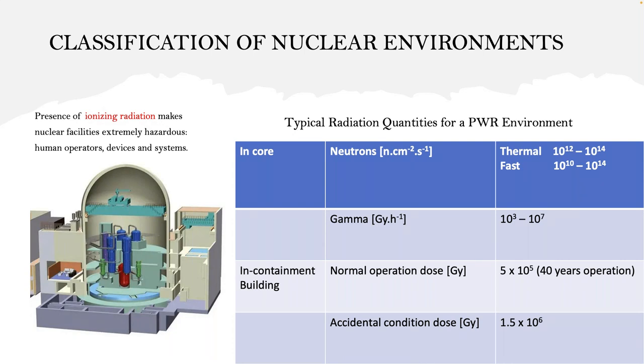Showing here the typical radiation quantities for a pressurized water reactor environment: the in-core area inside the reactor itself has neutron flux levels for thermal neutrons in the range of 10^12 to 10^14, fast neutrons in the range of 10^10 to 10^14, and gamma dose normally in the range of 10^3 to 10^7. That makes the environment very hostile, such that conventional electric sensors can be quickly disabled in that kind of environment.